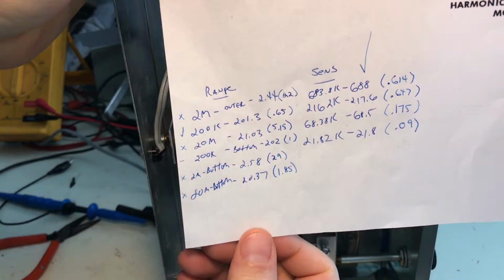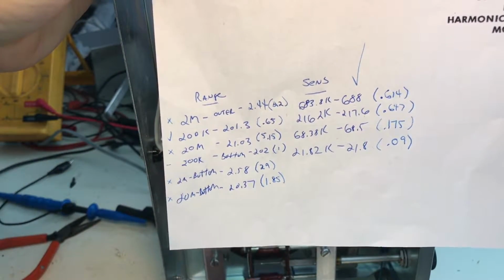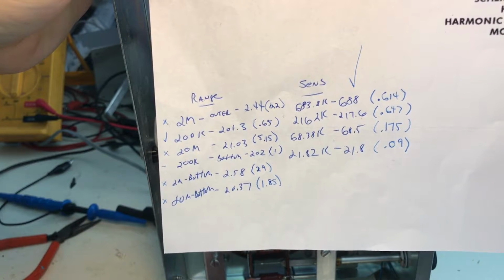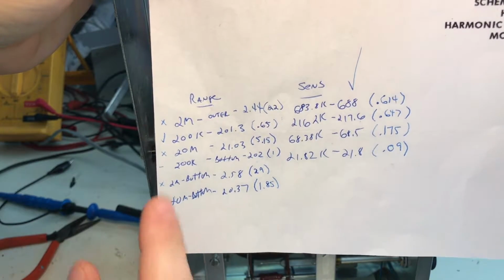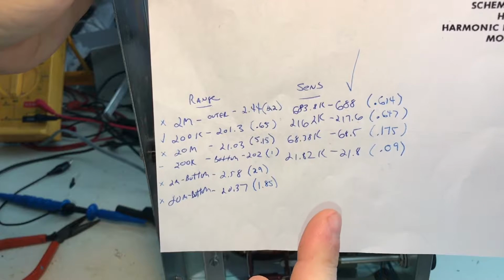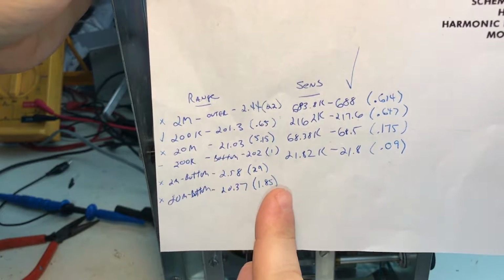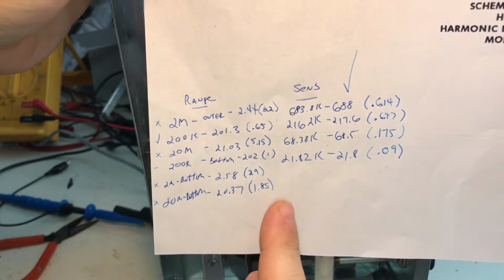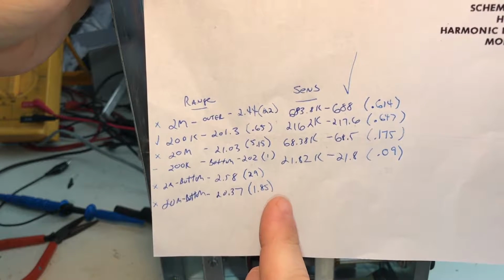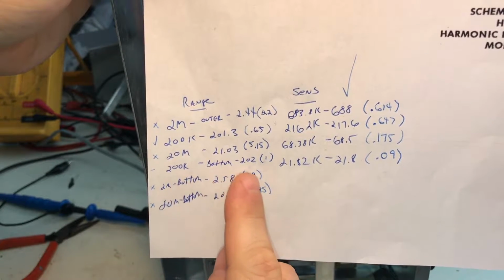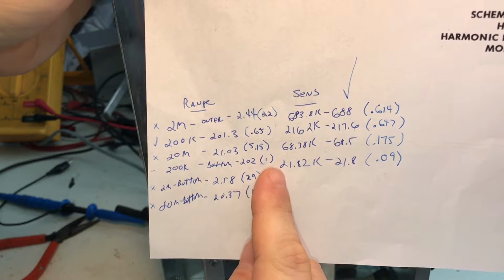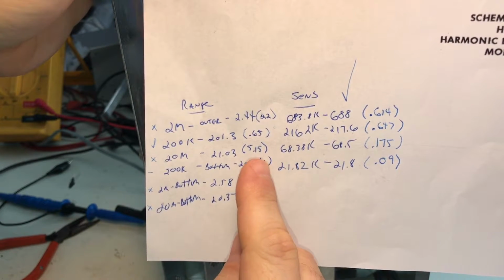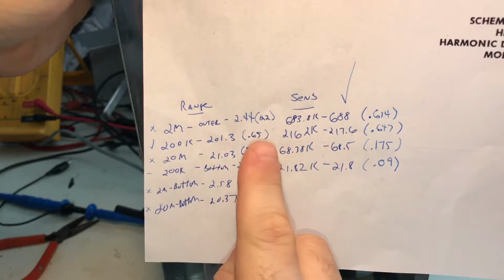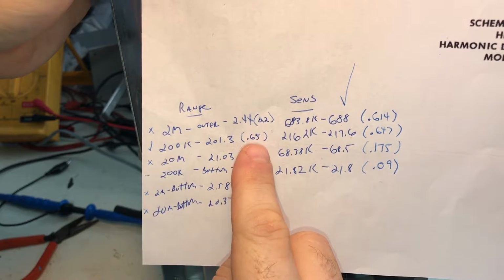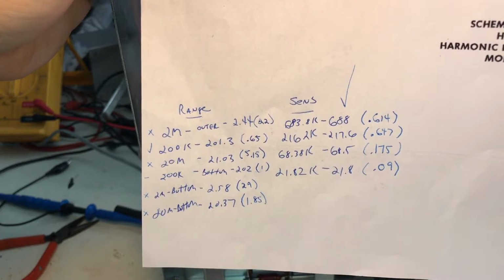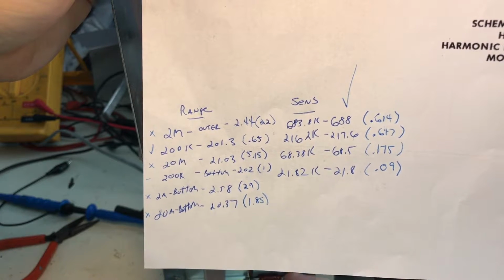The range switch, on the other hand, is terrible, especially on the 2 meg resistor, out by 82%. The other 2 meg is out by 29%. The 20 meg is out by 1.85, and the lower value ones, this one's by 1%, just barely making it. We could see this one 5.15%, and only one made it within standards, 0.65. So they're all garbage. They need to be replaced.